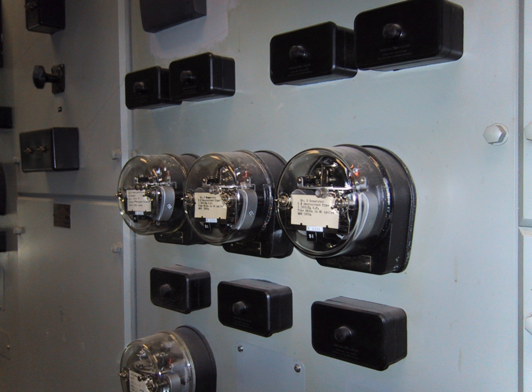Topic: Overcurrent relay. An overcurrent relay is a type of protective relay which operates when the load current exceeds a pickup value. It is of two types, instantaneous overcurrent IOC relay and definite time overcurrent DTOC relay. The ANSI device number is 50 for an IOC relay or 51 for a DTOC relay. In a typical application, the overcurrent relay is connected to a current transformer and calibrated to operate at or above a specific current level. When the relay operates, one or more contacts will operate and energize to trip a circuit breaker. The DTOC relay has been used extensively in the United Kingdom, but its inherent issue of operating slower for faults closer to the source led to the development of the IDMT relay.